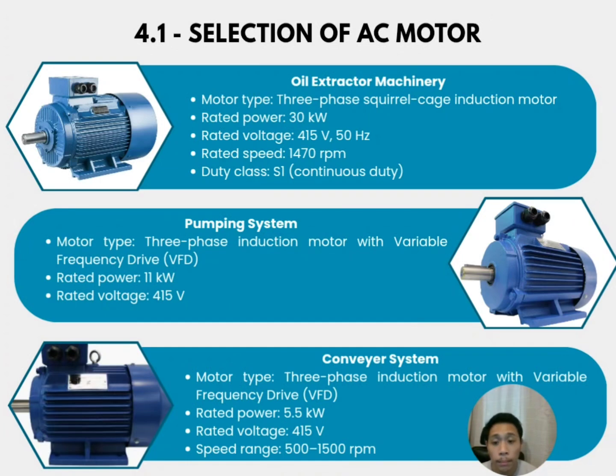The third one is the conveyor system. It's similar to the pump. This uses a 3-phase induction motor with a VFD also. This is our small unit, which operates at 5.5 kilowatts, reflecting the lower torque required to move the belt compared to the extraction or pumping. For the speed range, the VFD is critical here because it provides a wide speed range of 500 to 1500 RPM. This allows the operator to speed up or slow down the production line based on the volume of material being moved, ensuring the system remains flexible and synchronized with the rest of the facility.